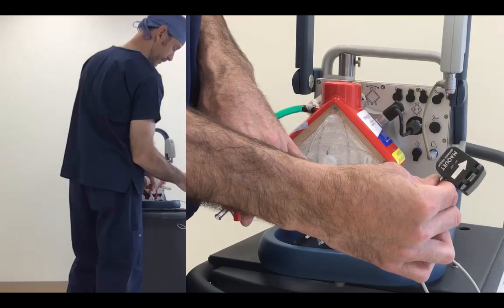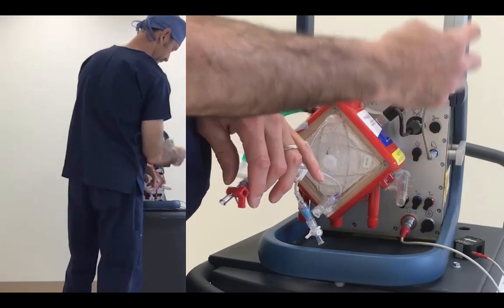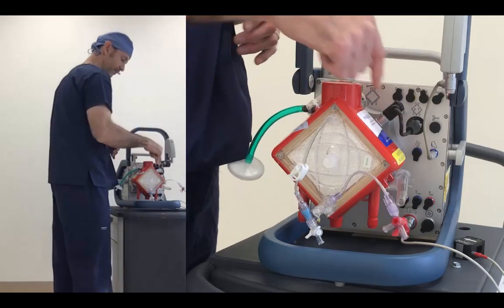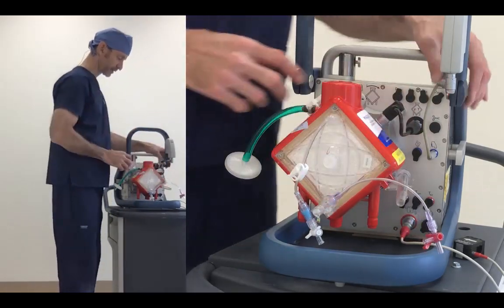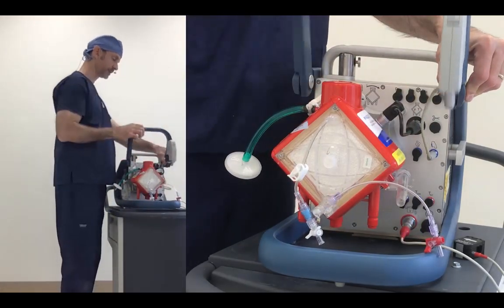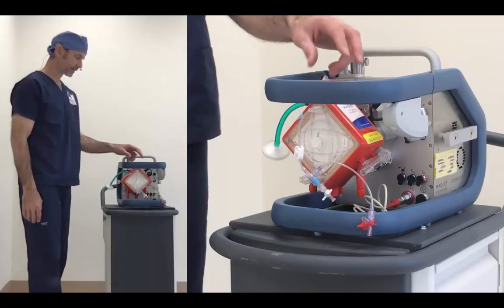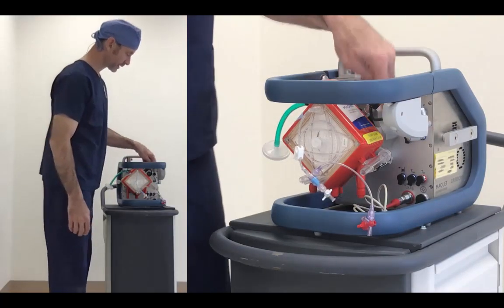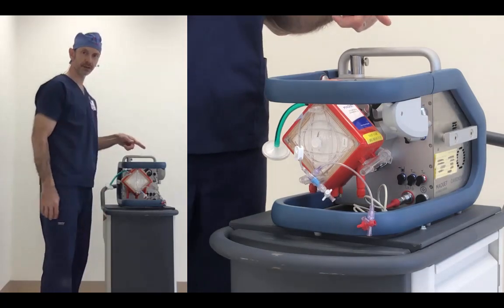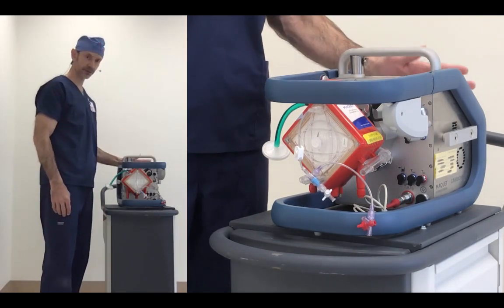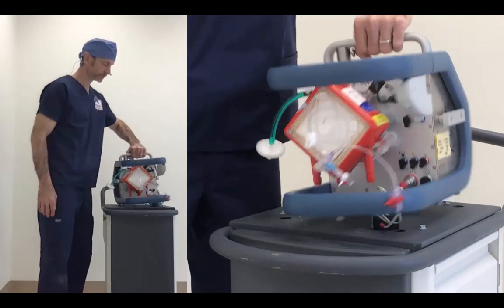With our arterial bubble flow probe connected and our venous set crit monitor connected and the data port for the oxygenator, we're done back here. So I'm going to press my 1 button, drop the door. Having placed our disposable and connected our electronics, why don't we spin this pump around now and take a look, turn it on and take a look at the console.